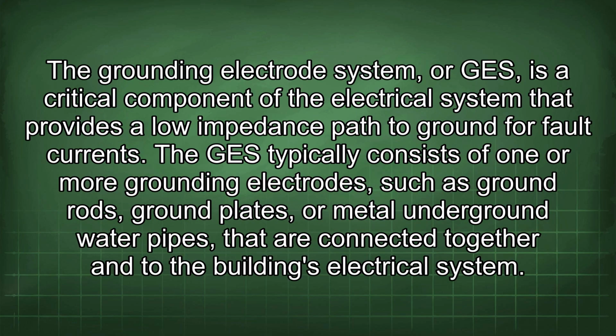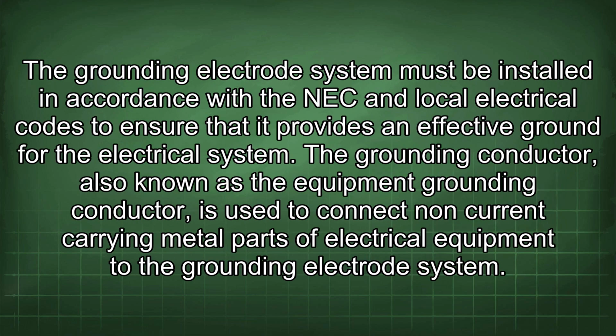The grounding electrode system, or GES, is a critical component of the electrical system that provides a low impedance path to ground for fault currents. The GES typically consists of one or more grounding electrodes, such as ground rods, ground plates, or metal underground water pipes that are connected together and to the building's electrical system. The grounding electrode system must be installed in accordance with the NEC and local electrical codes to ensure that it provides an effective ground for the electrical system.